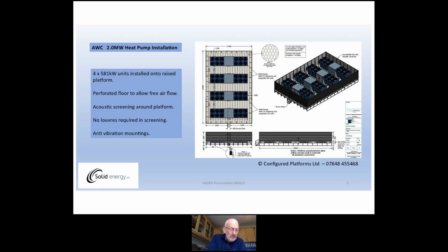We can combine heat pump units to increase output, and this slide shows a visual of a 2 megawatt air source heat pump. To give you some idea of the scale, this unit is 18 meters by 12 meters. 4 heat pumps sitting on a proprietary platform provided by Configured Platforms Limited that we've been working with on a number of projects. The floor of the platform is perforated to allow flow of air to the coolers, and the acoustic screening can be solid rather than louvered. So here we have a powerful air source heat pump with the potential to be located nearer to noise sensitive areas than you first may imagine.